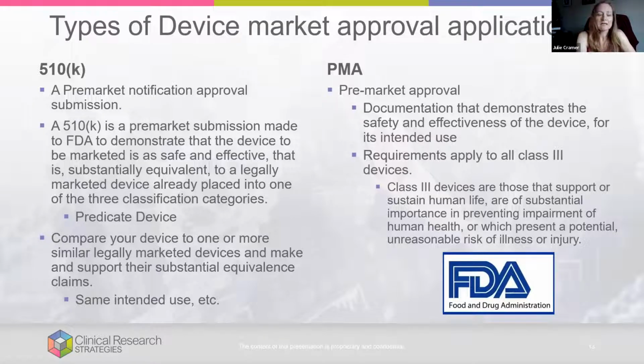So a 510K is again that which is tied to kind of a medium risk or a class 2 device. This is a pre-market notification approval submission. If you obtain a 510K, then it's 510K clearance. It's called a clearance. This is a submission made to the FDA to demonstrate the device to be marketed is safe and effective. You're going to hear that over and over again. Safe and effective is what the FDA cares about. It needs to be the same as or substantially equivalent to a legally marketed device already in place in one of the three classification categories.